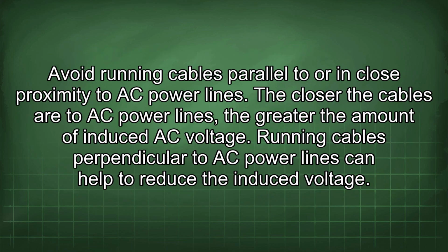Avoid running cables parallel to or in close proximity to AC power lines. The closer the cables are to AC power lines, the greater the amount of induced AC voltage. Running cables perpendicular to AC power lines can help to reduce the induced voltage.